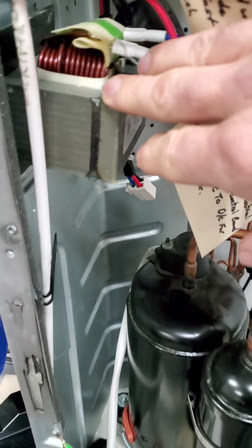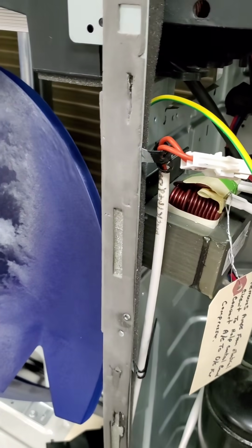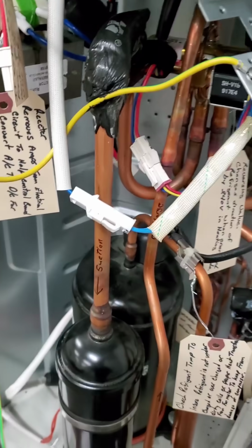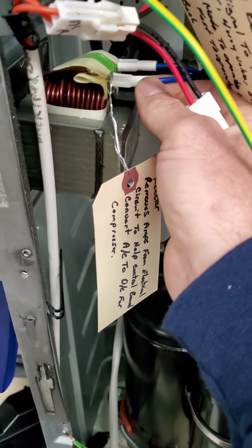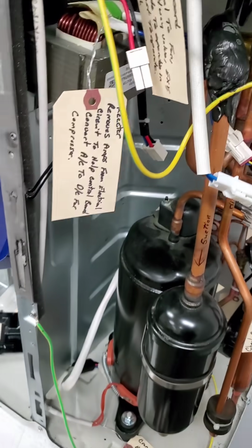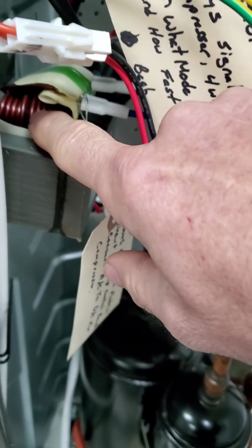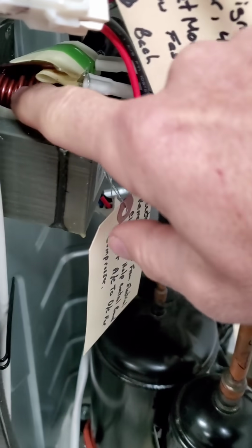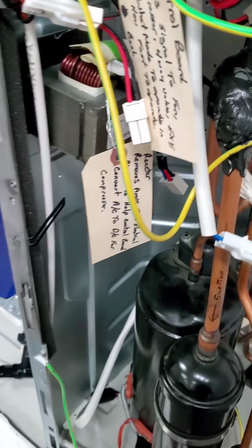You have a reactor. The job of the reactor is, it removes amperage from the control board to keep the control board from burning itself out. So you have voltage, but it removes the amperage. So here's a few things. The reactor should have very little resistance, 0 resistance, maybe 0.1 if anything. The only thing that can cause it to fail is if the shellac was to burn. You would have a power surge or something, and it was short one wire to another. Other than that, the reactors generally never fail.